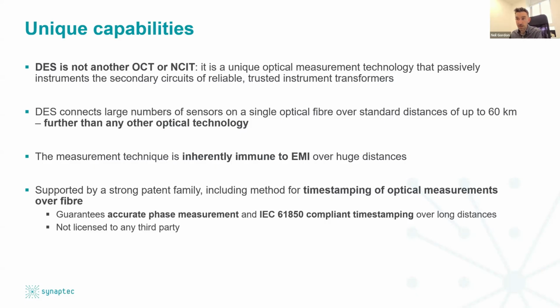Our measurement technique is inherently immune to electromagnetic interference. Again, unlike OCTs and NCITs, which are polarimetric measurements which are susceptible to interference. And what that means for us is that you receive exactly the same measurement that you took of your CT 60 kilometers away at the substation. It's not changed over that transmission period.